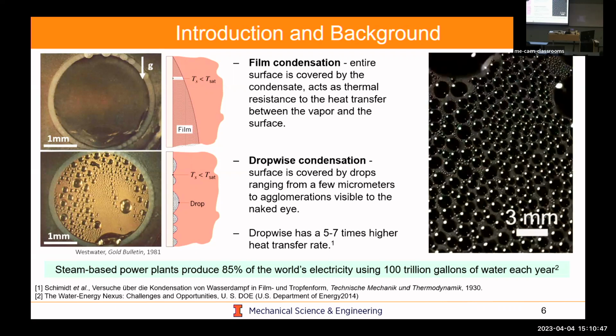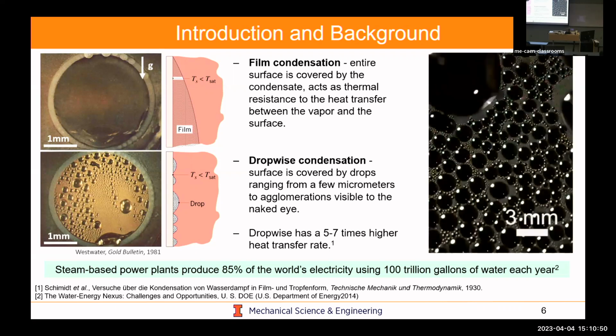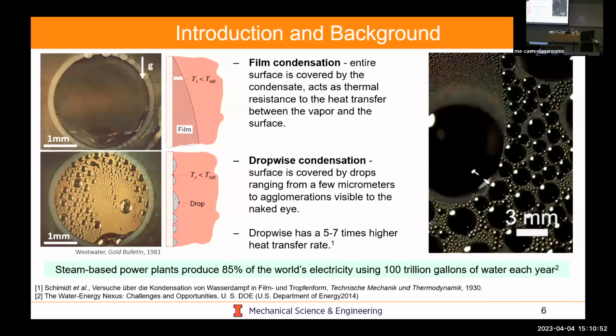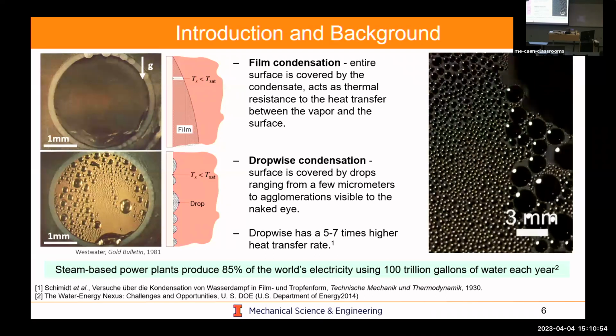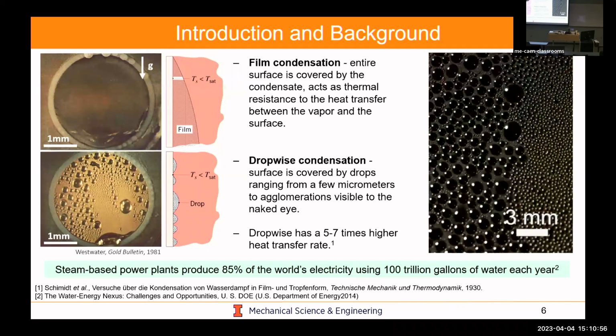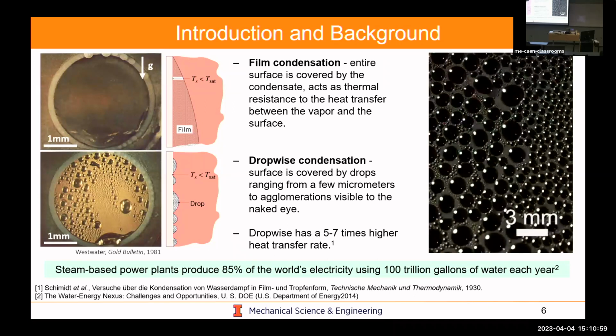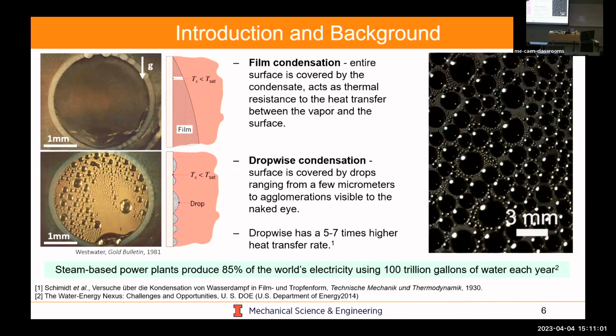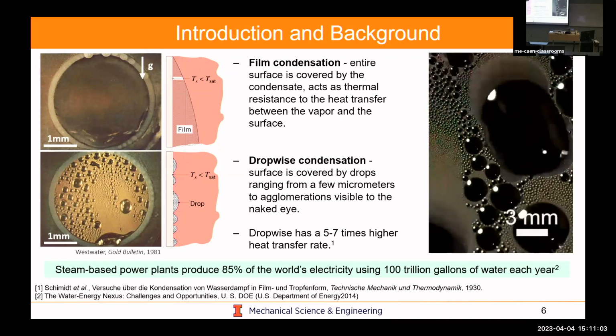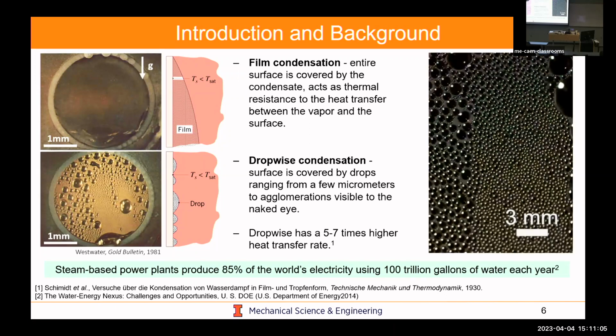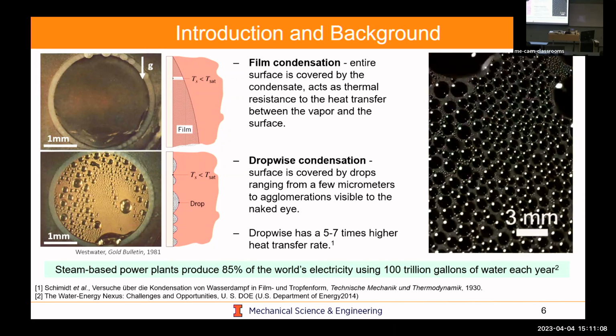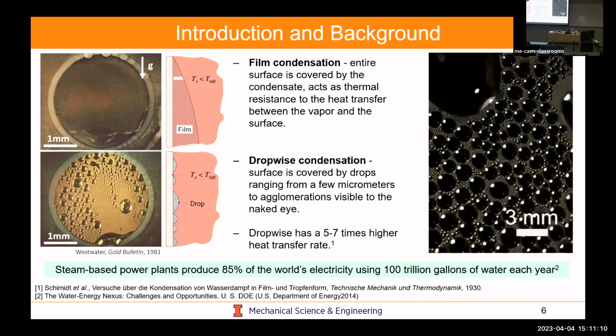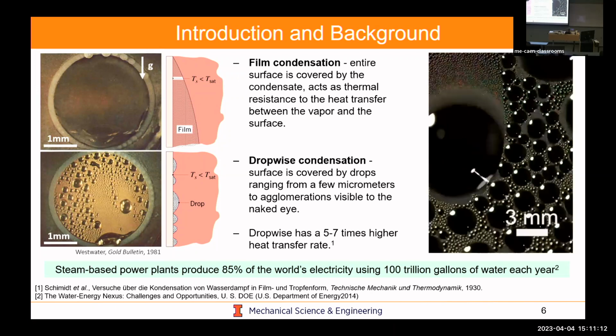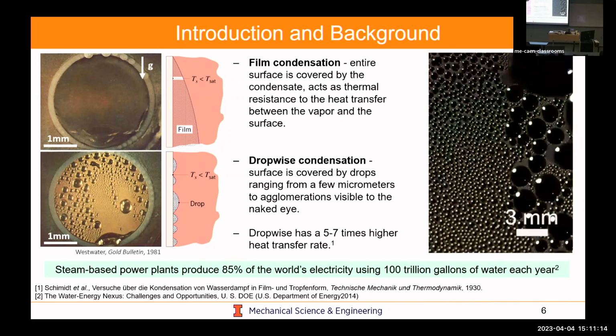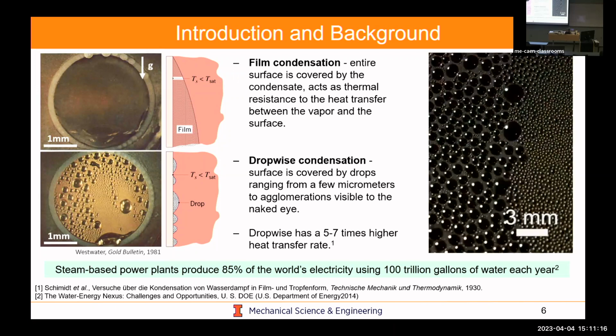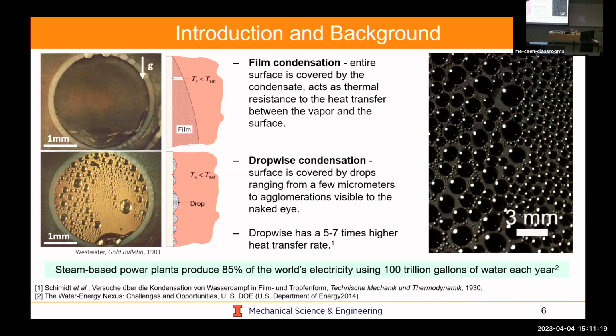In the 1930s, a gentleman by the name of Schmidt identified that if you put animal fat on the surface, you could undergo a thing called dropwise condensation. Essentially, you start forming discrete droplets, which once large enough, coalesce and shed because of gravity. When they shed, you see this cleaning process, which allows exposure of fresh vapor to condense on the surface. This highly transient process ends up giving you 5 to 7x higher heat transfer rates compared to film-wise condensers.